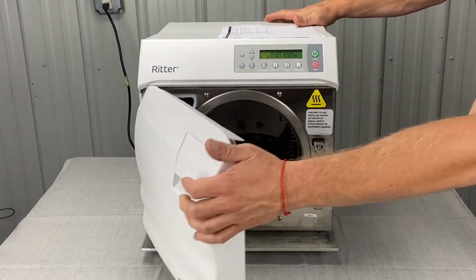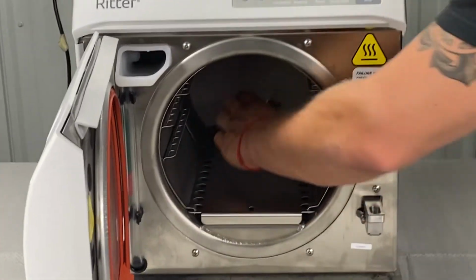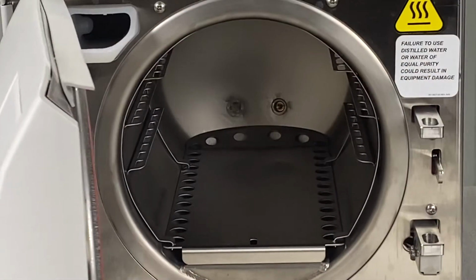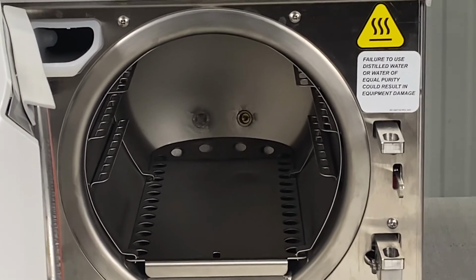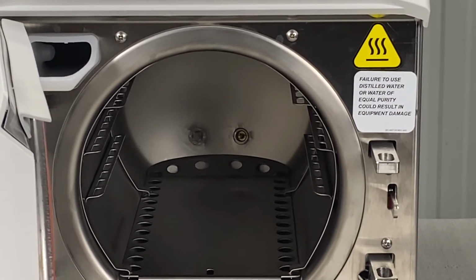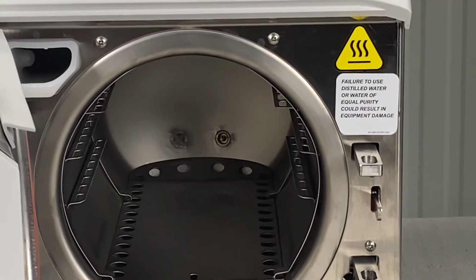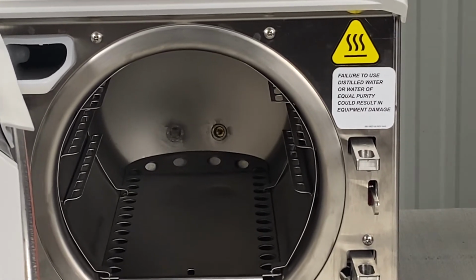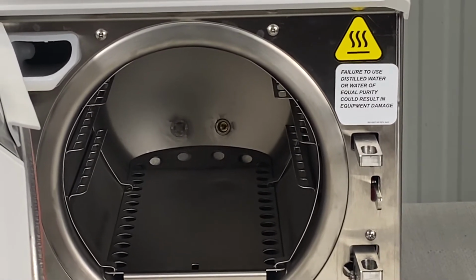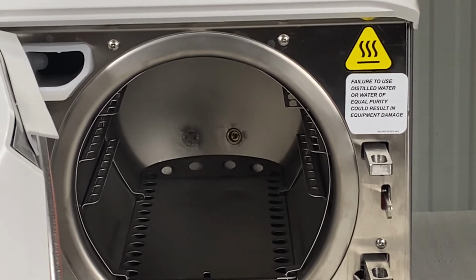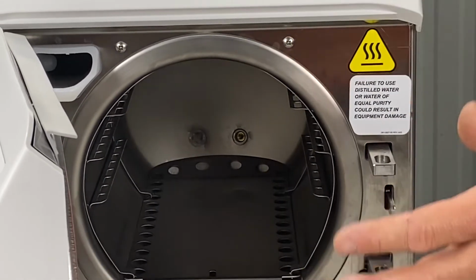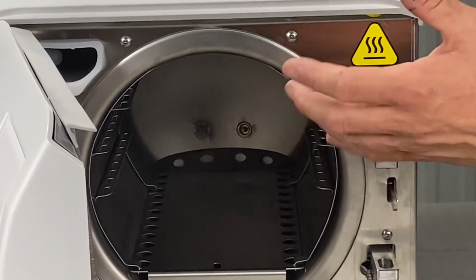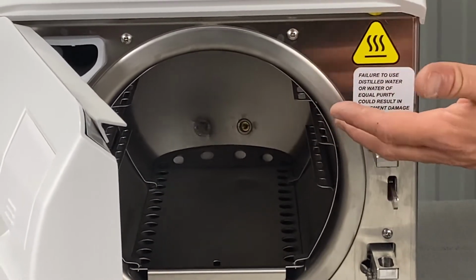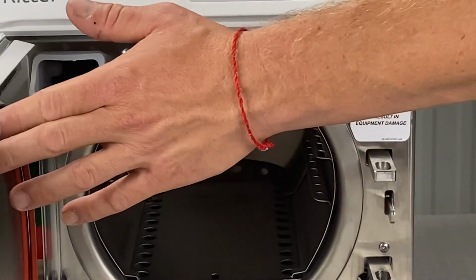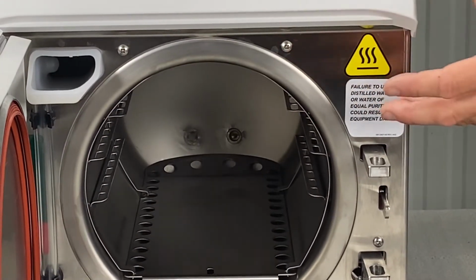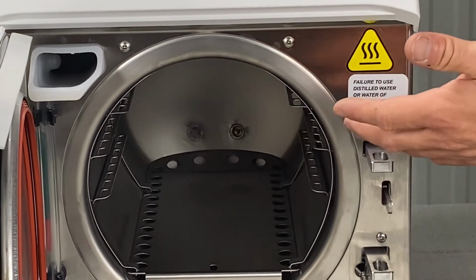So the temp sensor is the back center little post back here. We're going to want to clean that with Speed Clean, distilled water, and an abrasive pad. Scrub it off. Make sure nothing's melted on it or stuck to it. Whatever, wipe it off. Run an empty cycle. No instruments, no trays. They also could be part of the problem. If you're overpacking the unit, you got the trays all smashed on top of it, you got instruments laying on top of the temp sensor, you might get intermittent temperature sensor errors or issues like this.